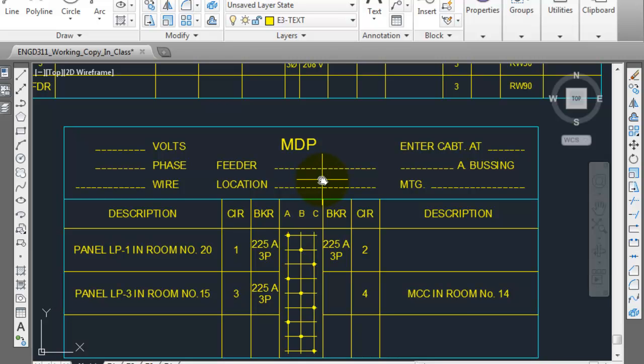This is not actually going to be your value. 645 amps is the capability for a 1250 kilo circular mill. That's KCMIL. If you look in table number 2, top left-hand corner, you'll see size AWG, comma, KCMIL. That's actually short for kilo circular mills. Let's call it KCMIL. You're going to use 1250 KCMIL. So that's what you're going to put in the feeder.